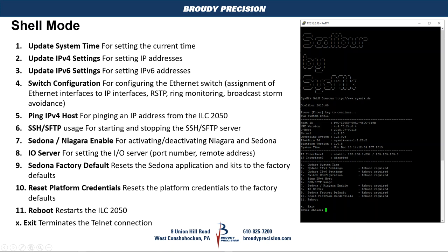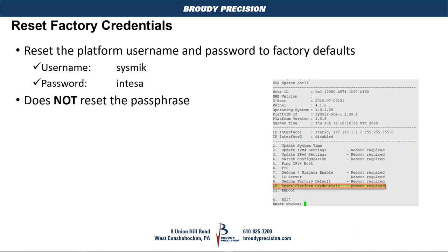One thing that often comes up with tech support is: I don't remember my platform username and password — how do I return to that? With the ILC 2050, which is different from the JACE 8000, you can go into shell and reset your platform credentials without doing any major surgery. Using option 10, it resets the username to 'sysmik' and the password to 'intesa'. Note that it does not reset the passphrase — the passphrase is locked down more tightly. If you don't know the passphrase, the procedure we're going through today — resetting to factory defaults — would be your way to reset it.